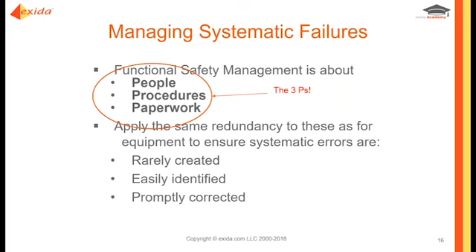For example, if we require some critical safety equipment to be calibrated, we might say the procedure has a 4-eyes requirement: the person responsible for doing the calibration carries it out, and then a supervisor or senior person checks it, just to make sure it's been done correctly. If we do this right, we won't create problems, or will rarely create them, and we can easily identify when we do and correct them.